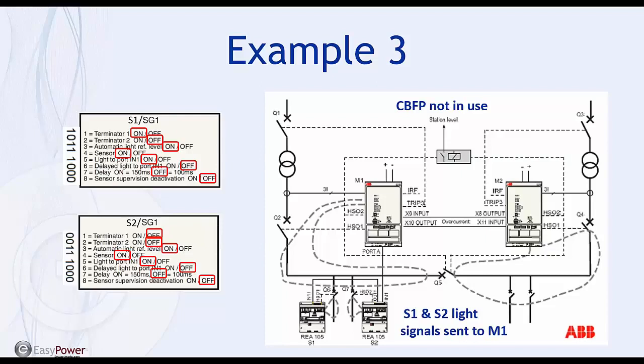So, if safety should always be the priority, this is a case where this switch is available, so it can act like an RE103, and you can send light back to the main unit. If the fault detector is picked up, then you're going to trip Q2, so you're not going to have that added incident energy that's a result of having that selectivity in the event of a breaker failure. So that's just to let you know that that option is out there.